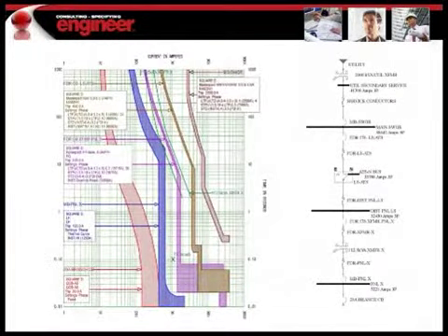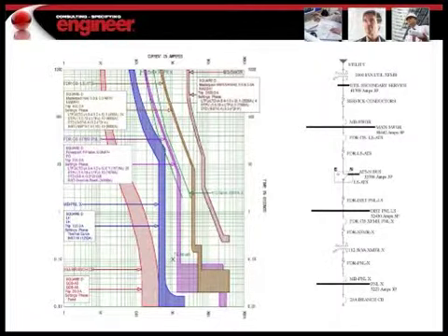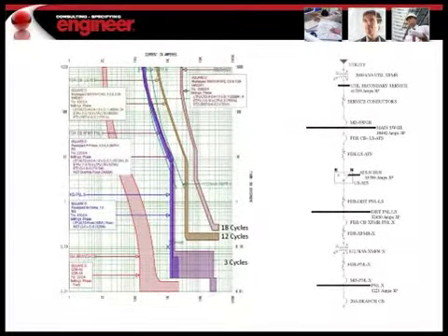So anyway, this slide shows that we don't have selective coordination between the branch breaker and the upstream main breaker in the power panel, and we also don't have coordination in the instantaneous region between the breaker ahead of the transfer switch and the breaker serving the distribution transformer. So with a few adjustments to some of these breakers, we can manipulate the settings to a point where we do achieve selective coordination. And you can see here that the breakers in the system do selectively coordinate.